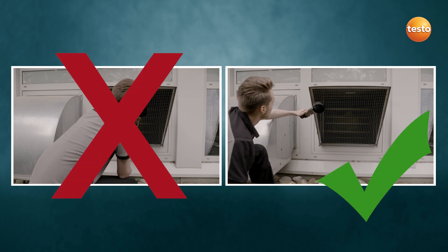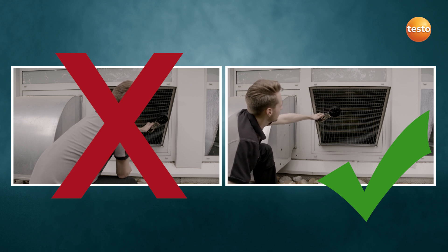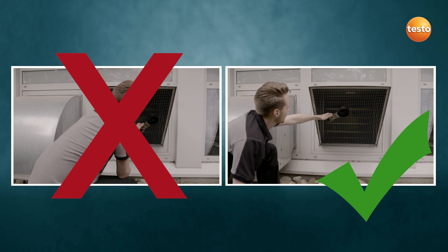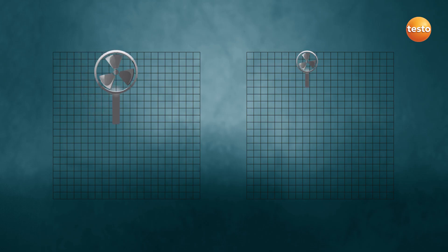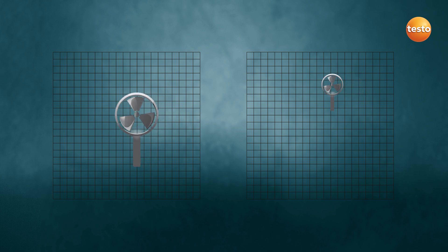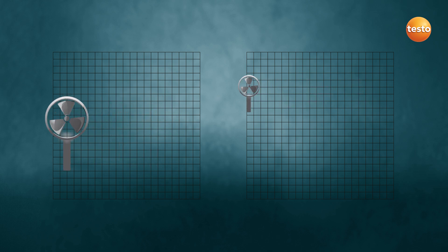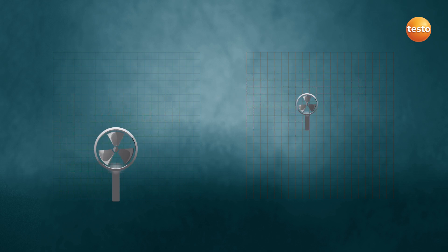The best method is to move the vane across the grill surface at a distance of 5 cm. Vanes with 100 mm diameter are better suited to measuring than instruments with smaller vanes, as the flow values are integrated and averaged over a larger area.